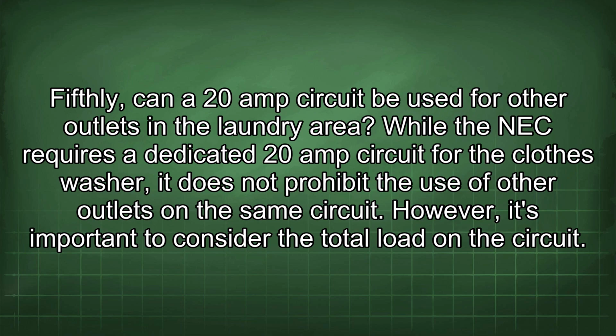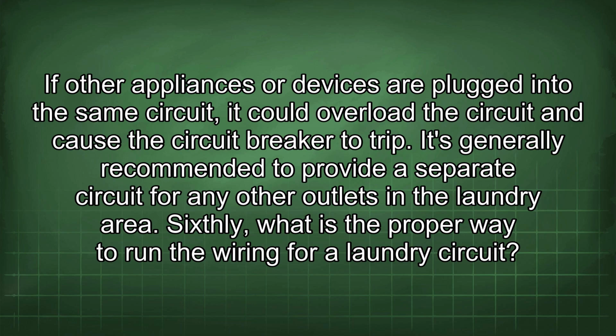However, it's important to consider the total load in the circuit. If other appliances or devices are plugged into the same circuit, it could overload the circuit and cause the circuit breaker to trip. It's generally recommended to provide a separate circuit for any other outlets in the laundry area. Sixthly, what is the proper way to run the wiring for a laundry circuit?